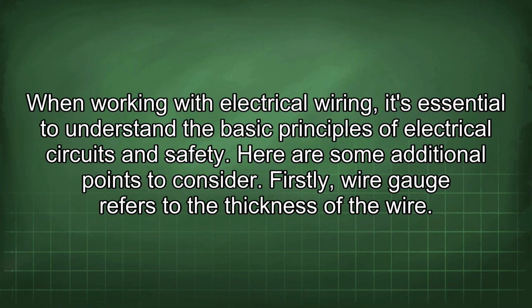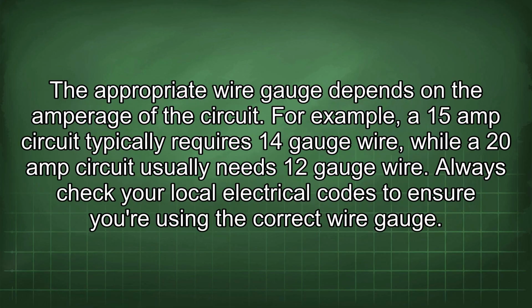When working with electrical wiring, it's essential to understand the basic principles of electrical circuits and safety. Here are some additional points to consider. Firstly, wire gauge refers to the thickness of the wire. The appropriate wire gauge depends on the amperage of the circuit. For example, a 15 amp circuit typically requires 14 gauge wire, while a 20 amp circuit usually needs 12 gauge wire. Always check your local electrical codes to ensure you're using the correct wire gauge.